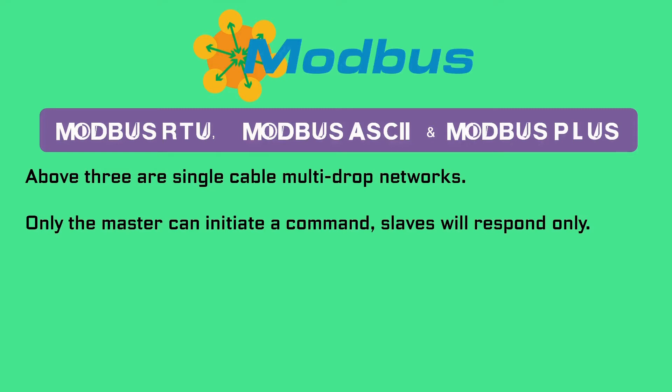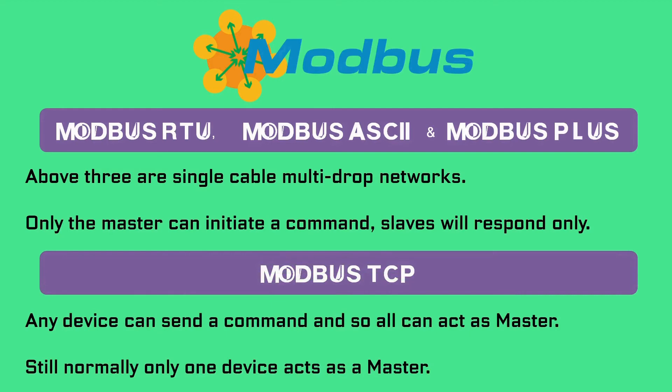In these three, only the node assigned as the master may initiate a command. All other devices are slaves and respond to requests and commands. For the protocols using Ethernet such as Modbus TCP, any device can send out a Modbus command, thus all can act as a master, although normally only one device acts as a master.